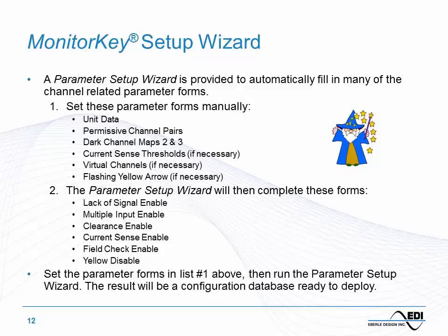The forms to complete manually are listed in item one — unit data, permissive channel pairs (the conflict matrix), and some others that may or may not be needed. Run the setup wizard and it completes the six forms listed in item two, then write it to the key and you're ready to go. Most programming errors I've found are in the forms that the wizard will do for you. If you give the wizard accurate inputs, it will generate very accurate programming.